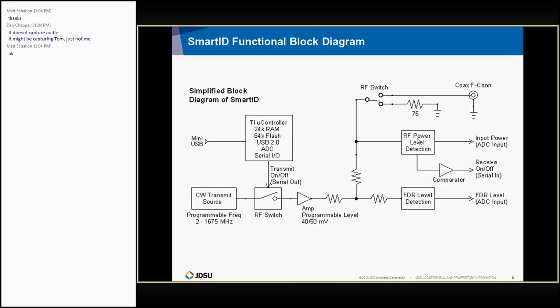And the last thing I want to point out is the RF switch up in the right, up at the top. The Smartid has the capability of switching itself to a 75 ohm internal termination for calibration purposes and to establish a noise floor, and a reference FDR before it actually switches out to the cable. But when it's in that reference position that it's shown at right now, it also has a secondary effect that is used to good effect, where it basically makes the probe a high impedance termination and generates a strong reflection. Whereas when the switch is in its normal position to the top, it will act as a normal termination in receiving. I'll show later how that comes into play. That's used to identify the position of remote probes across the network.